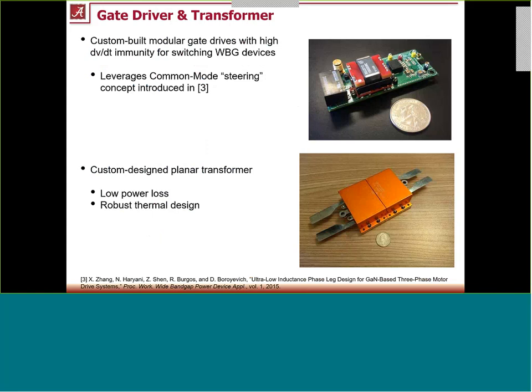One of the major challenges was proximity effect in the windings at these high frequencies. The DC resistance of the winding was rather small compared to the AC resistance at 100 kilohertz, and the current crowding we saw at high frequency between the primary and secondary windings was such that the windings would get very, very hot and then heat up the core, and then the core would begin to saturate.